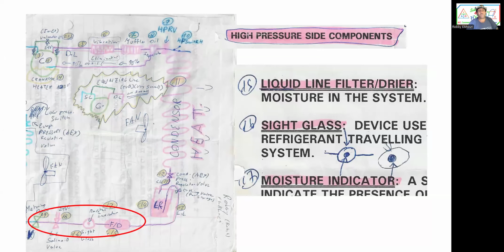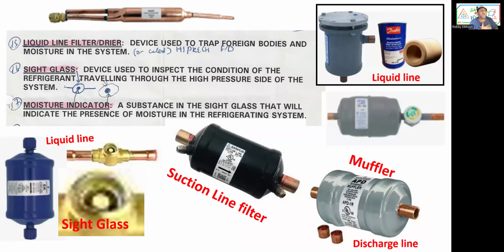Next slide. Okay, the filter dryer, sight glass, and moisture indicator. All right, so the filter dryer's job is to trap dirt and moisture in the system. The filter traps all the dirt in the system, and the dryer picks up the moisture, because moisture is our enemy, our second enemy. First enemy is heat, second enemy is moisture. All right, the sight glass is to look at the Freon inside and to see if it's bubbling or not. And the moisture indicator is inside the sight glass.